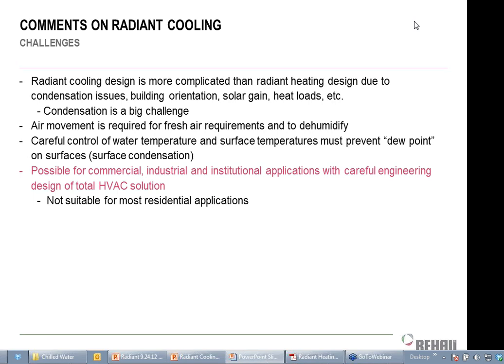We tend to not recommend it for residential applications, and that's not because we can't do it. It's just because we're worried that the people operating the system won't be able to understand it, and the controls that are put on there won't do a good job of policing it, and we could end up hitting the dew point. So in concept, we can do it. We just haven't done any that way, at least in our office.